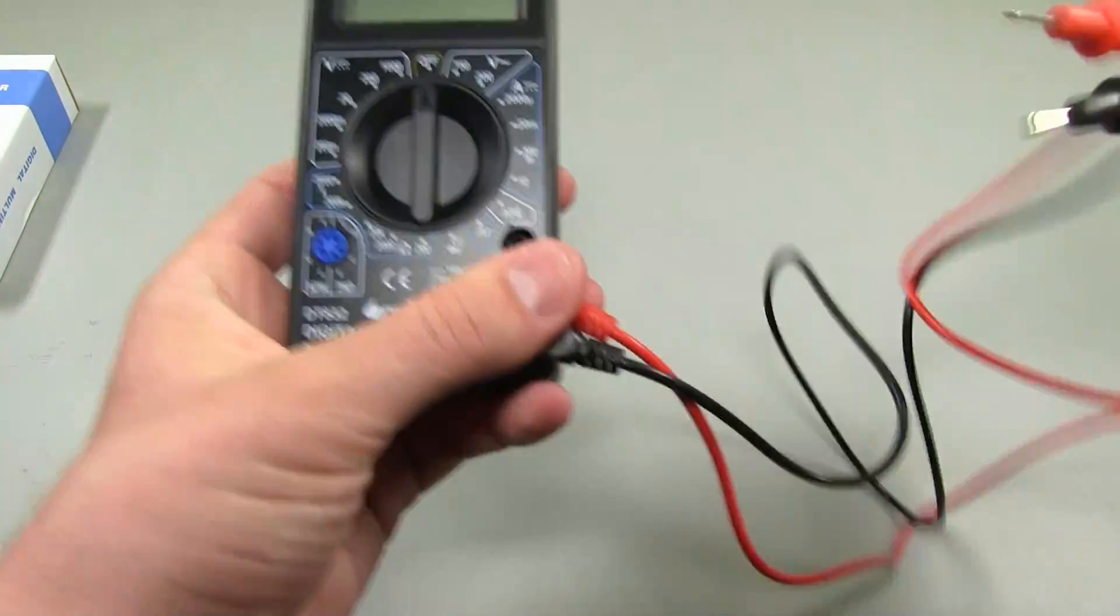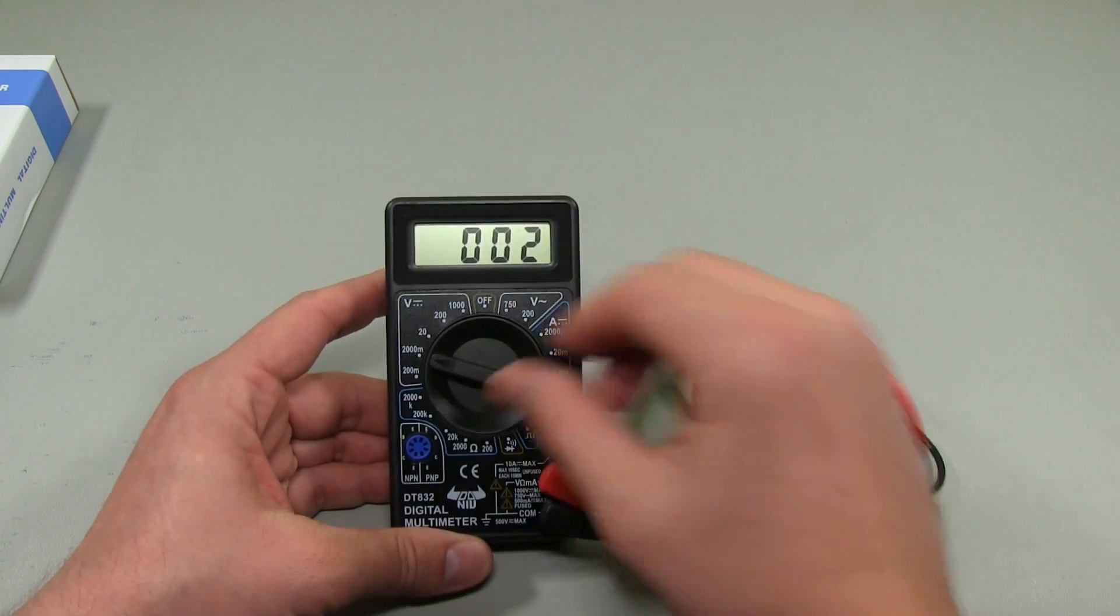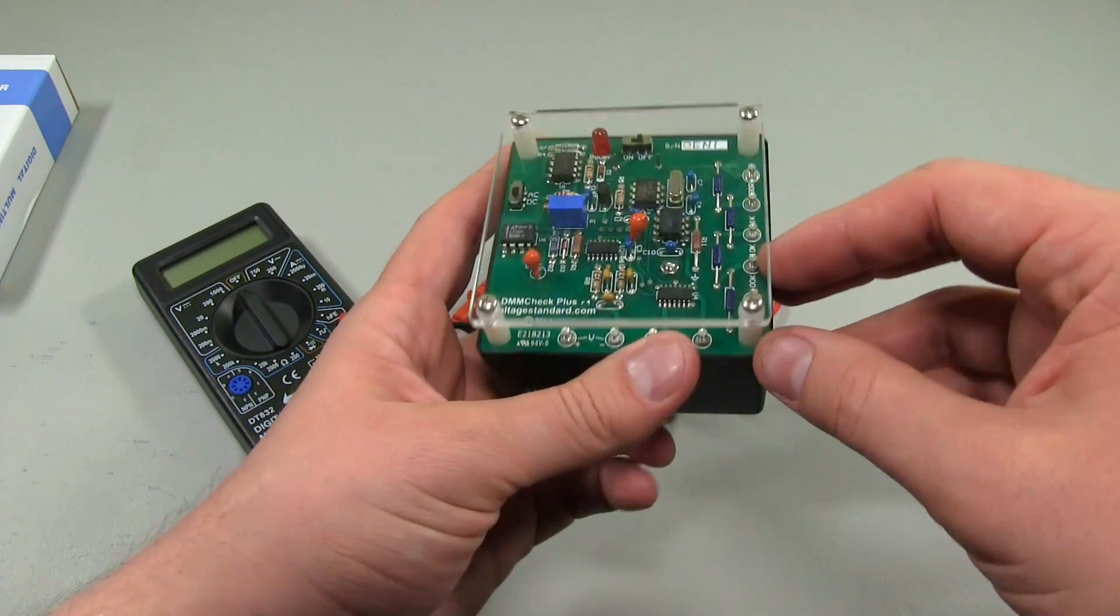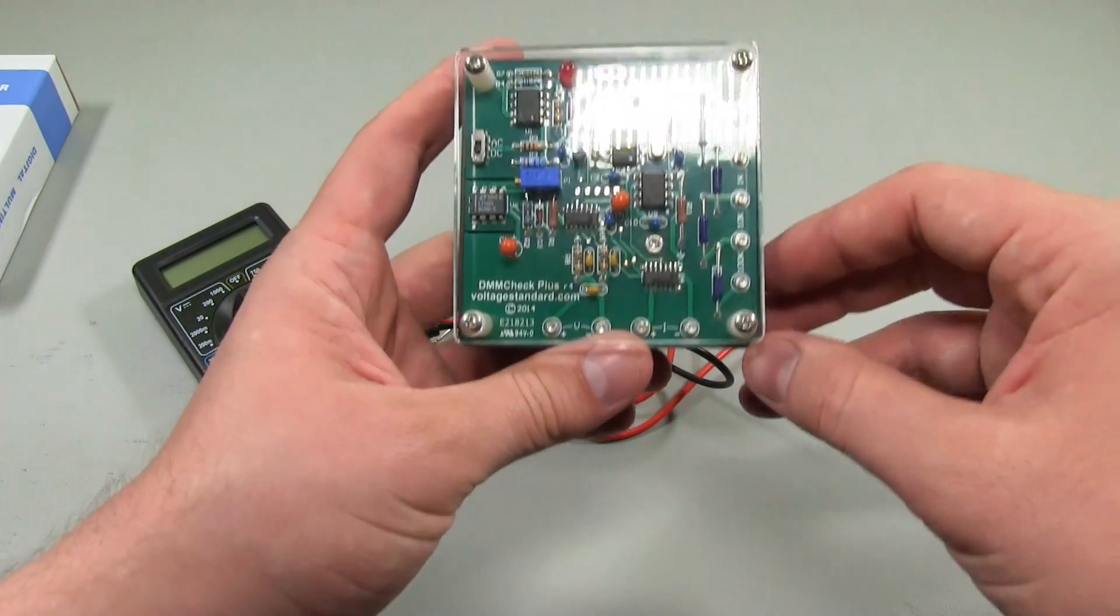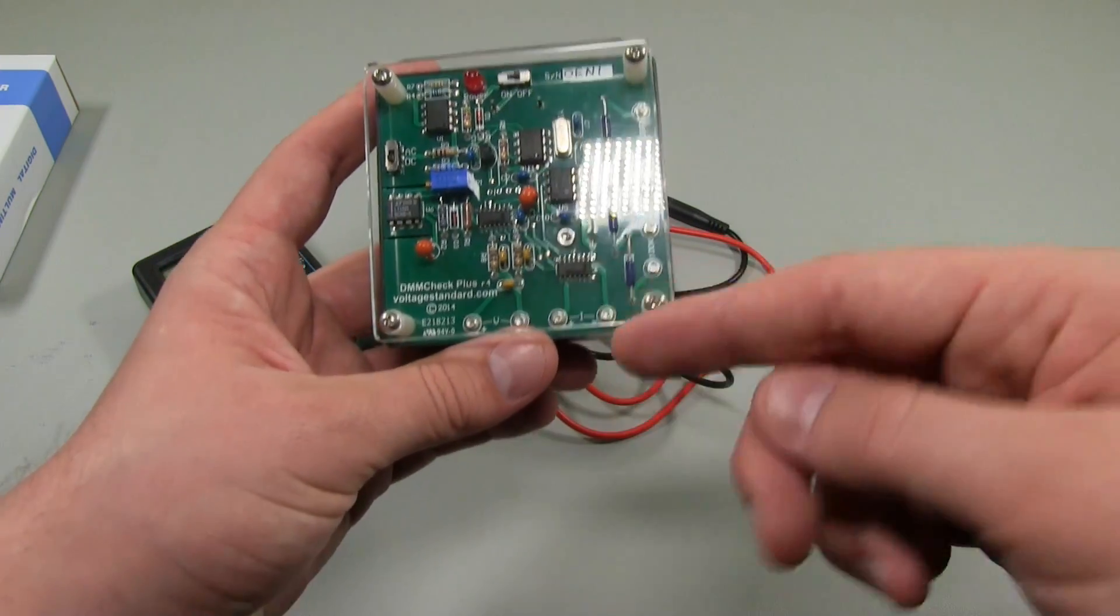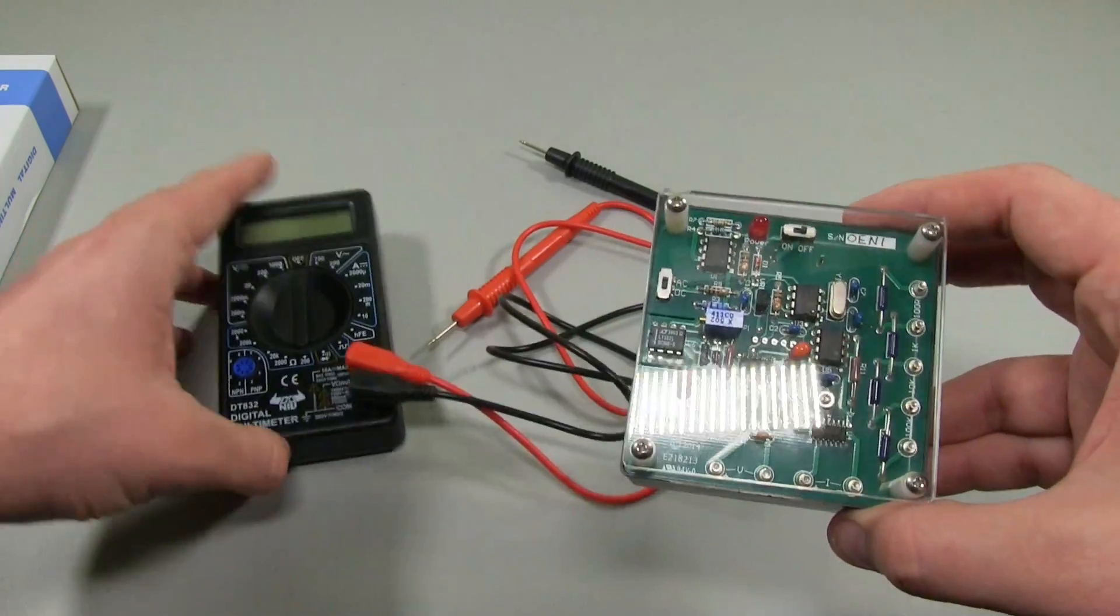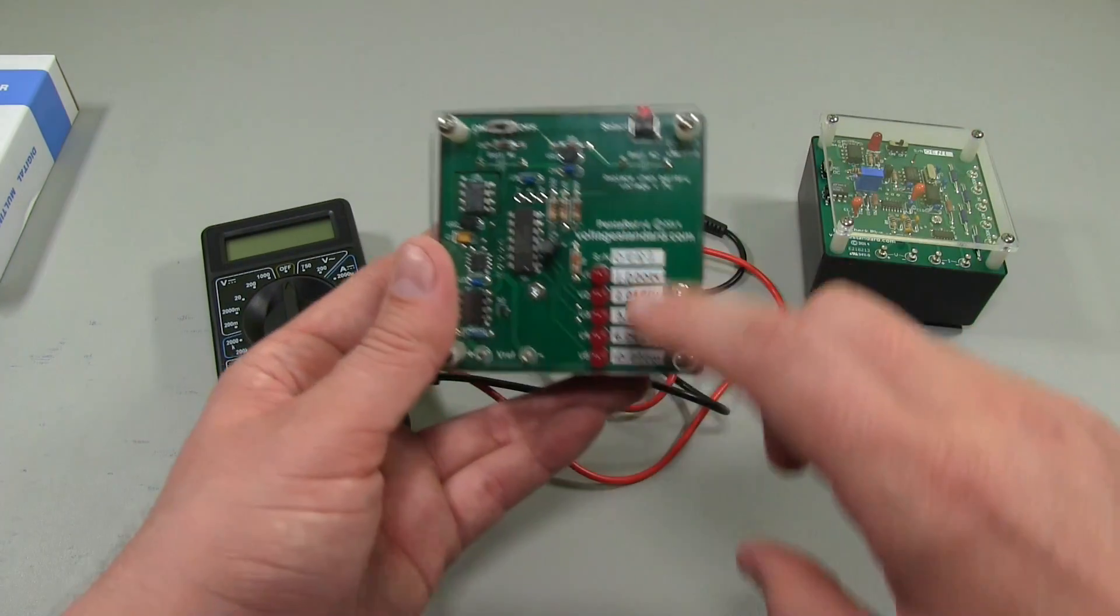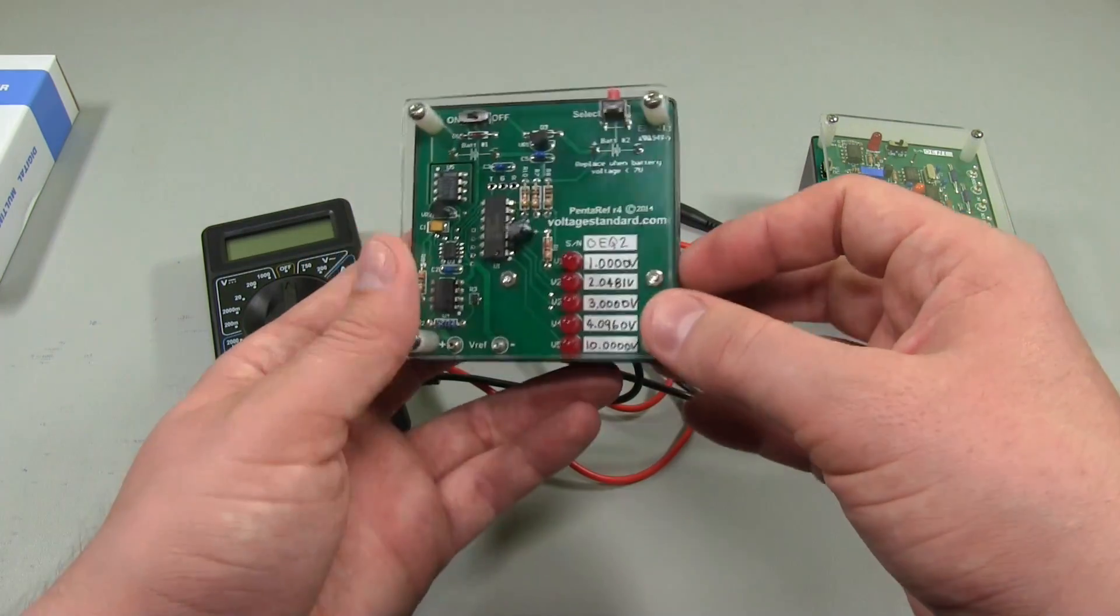Today we're going to be testing this multimeter, the accuracy and the measurements, with this DMM Check Plus from voltagestandard.com. This is pretty good because it does AC and DC voltage and current, it does frequency, and some precision resistance here as well. So we can test most of these functions with this one device. I can also test with this, which has got five custom DC ranges that I specified when I ordered this.